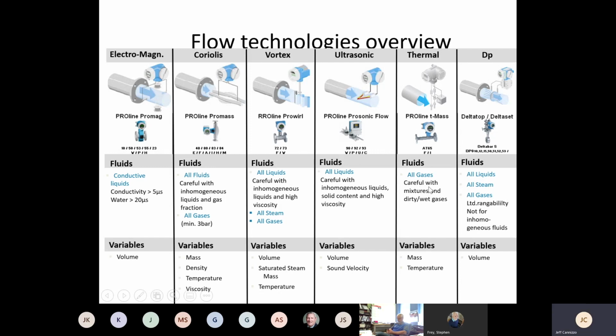Thermal mass meters, all gases. In the case of Endress+Hauser, we do not do a thermal mass for liquids at all. It's all types of gases. We can do mixtures with certain meters. You do have to be careful with moisture in your gas. It will affect a thermal mass meter as far as the output, but the output is a true mass reading, and you can output temperature as well. And again, differential pressure can be typically applied to most any application. Obviously, there's limits on rangeability and some things like that that you need to be aware of.